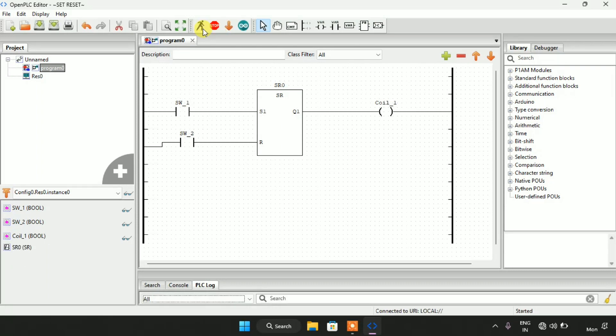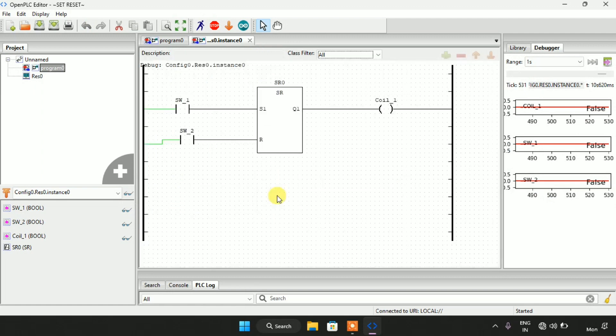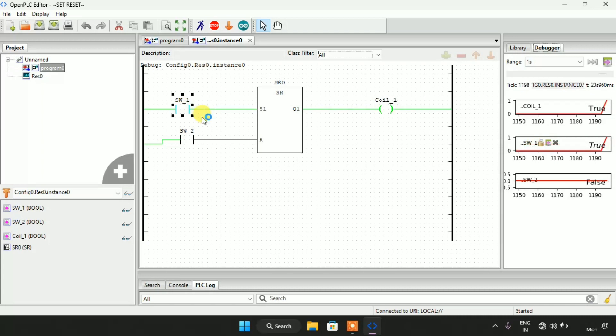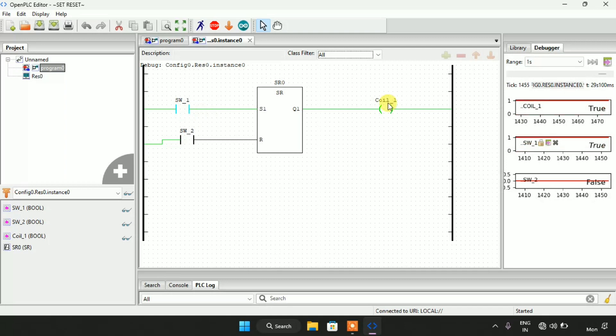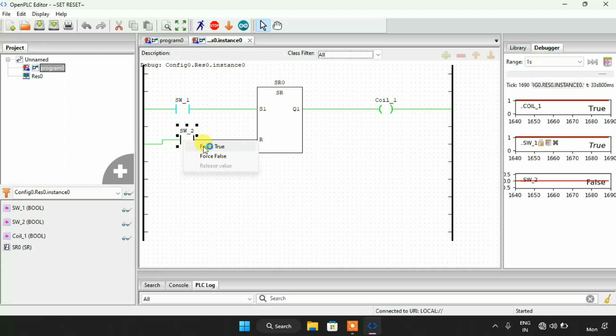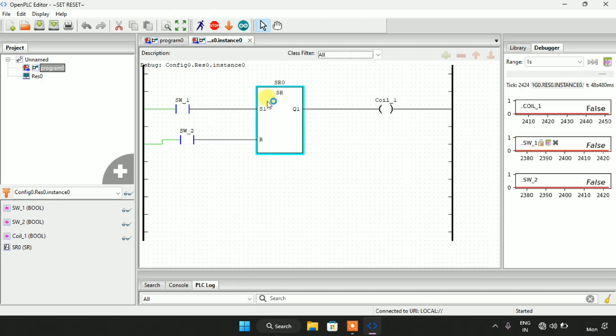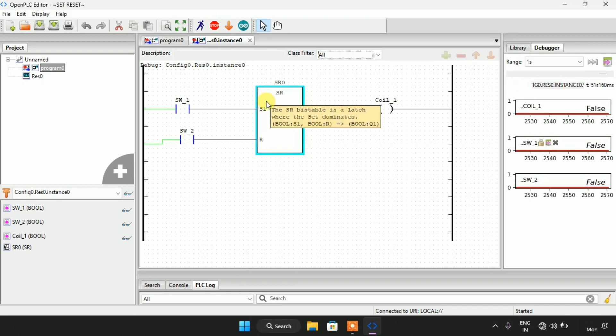I will start the simulation here. The simulation is complete. I will click on the glasses here and drag this a bit up. You can see on the right side the coil and these two switches. Let's see how SR works. When I modify Switch First to true, the coil will go true. And when I modify Switch Second with reset, the coil first is still true. In SR, the set dominates in this block. The SR bistable is a latch where the set dominates.